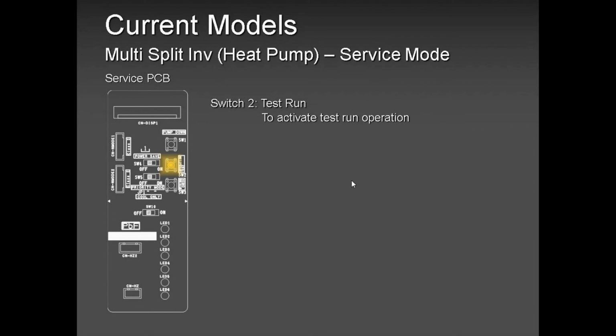So basically, when you press that pump down button, the unit will run at a fixed compressor frequency speed. The compressor will run. The unit will operate in cool mode. All the expansion valves will be fully open. All the gas will be collected into that compressor, so make sure you close the liquid line. And once you are getting closer, by the indication of these lights here, as you can see them blinking, 3 minutes remaining, 2 minutes remaining, 1 minute remaining. As it's getting closer to 1 minute, make sure you're ready to close your suction line. And that's about it. You're done. If you need to cancel for whatever reason, in between, you can always shut it down by pressing that button again.